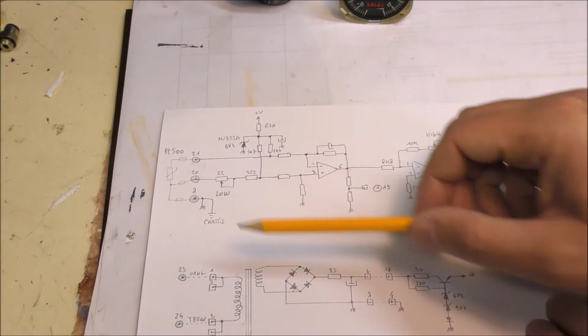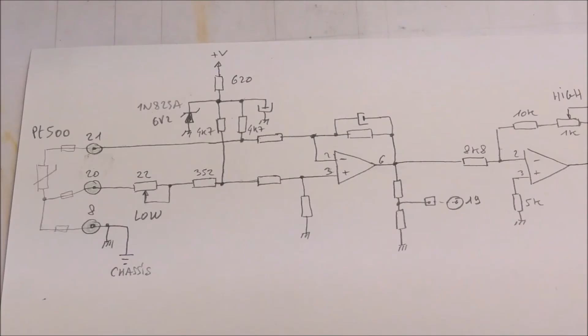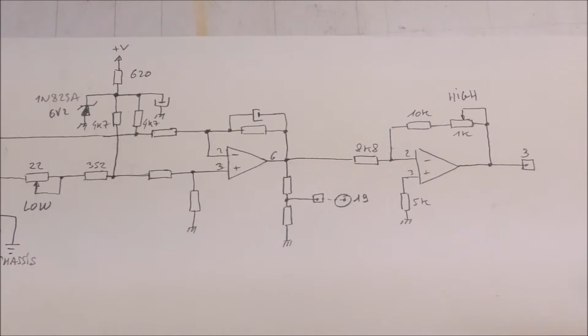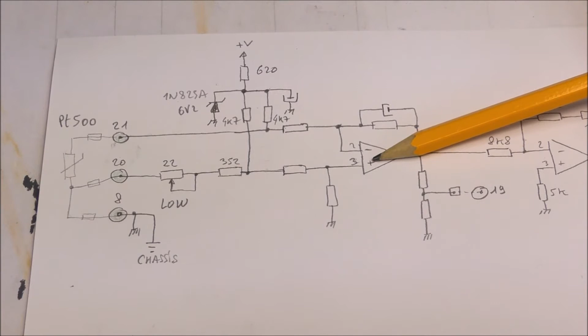This permits having 0 volt at the output when the temperature is minus 70 degrees. This is the adjustment of the low scale, and the high scale is adjusted by the gain of the final amplifier here. This amplifier should have good performance in terms of offset drift, etc.